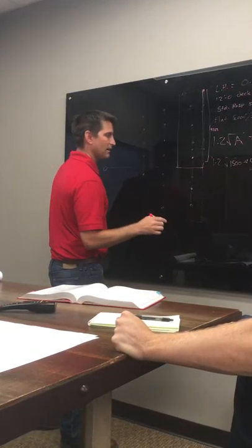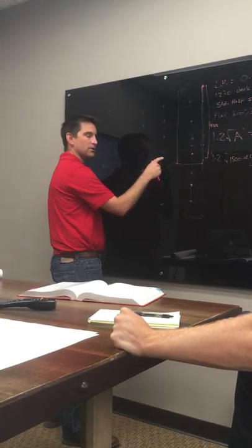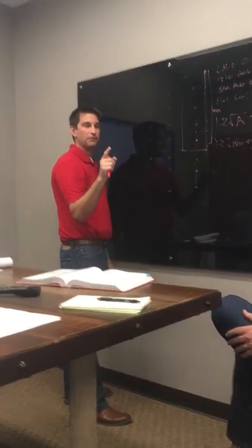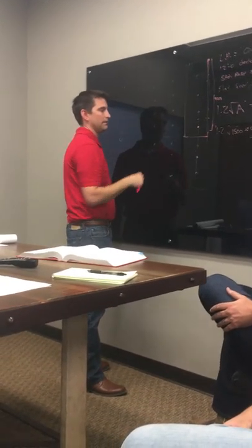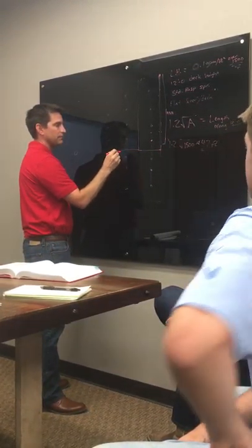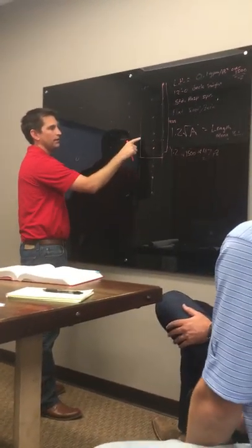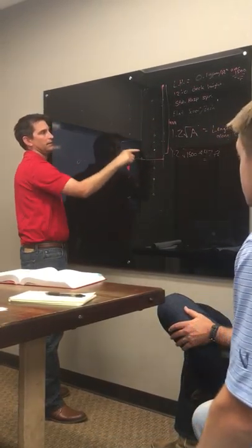What is that saying? I'm going to go to the next adjacent branch line, which is this one. I've already got my 47, so I'm down to here. The first head I pick up is going to be the one closest to the main. Which one's closer to the main? This one, this one, this one, or this one? The bottom one. That one. I'm actually going to pick up that sprinkler first. So now I'm going to come over halfway, halfway between all of them, right? Because that's the area of the sprinkler. And my remote area would look like that.